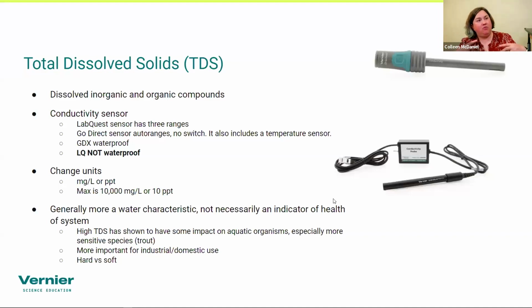And one important aspect to think about with measuring total dissolved solids is that the conductivity probe is a very common probe used by chemistry classes. And the units that they use most often are going to be microsiemens. Most students are going to either laugh at that, or be like, what the heck is this? I've never seen this before. And as an environmental science teacher, I went, what is this unit? I have never seen it before. But what's great is you can change the units on the sensor so that it's reading milligrams per liter or parts per thousand. And so I recommend you actually have that written into a protocol to change those units. In the labs that we have written for doing conductivity measurements, that is part of the procedure, to change the units to milligrams per liter.